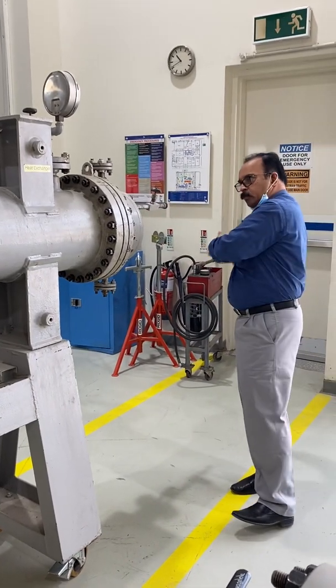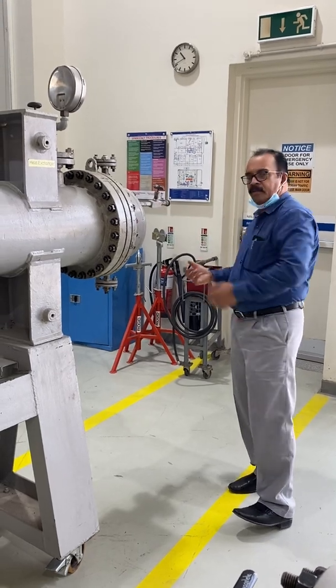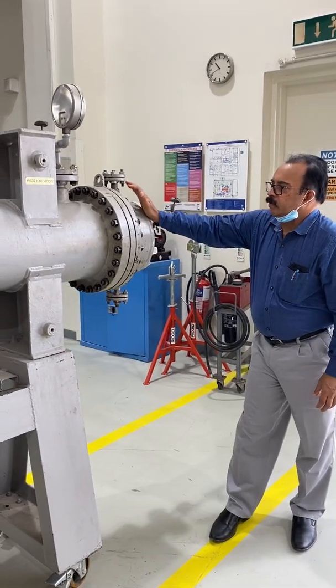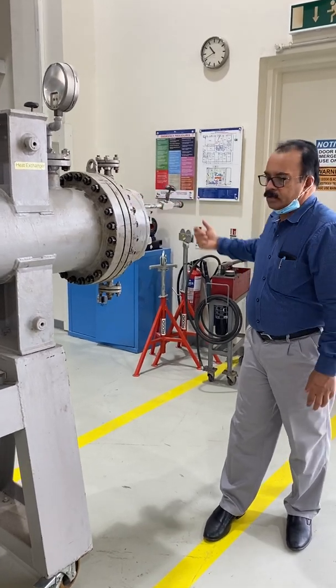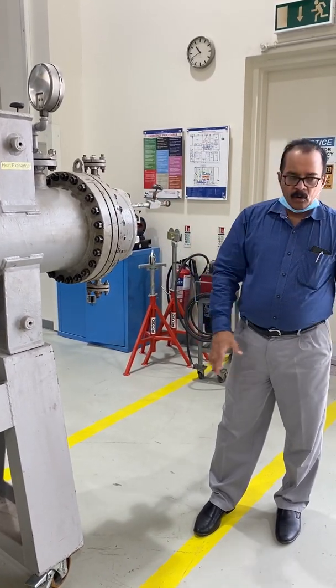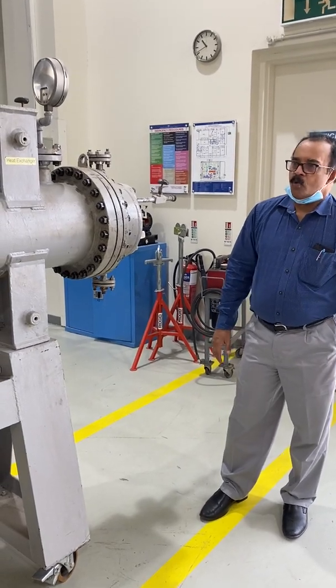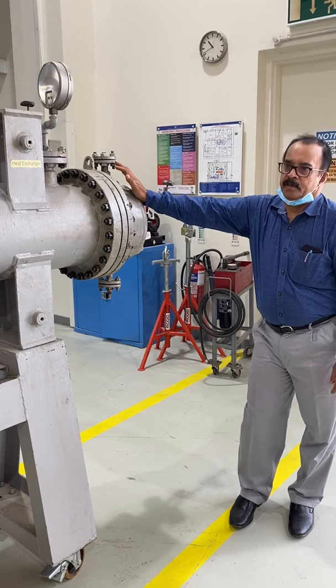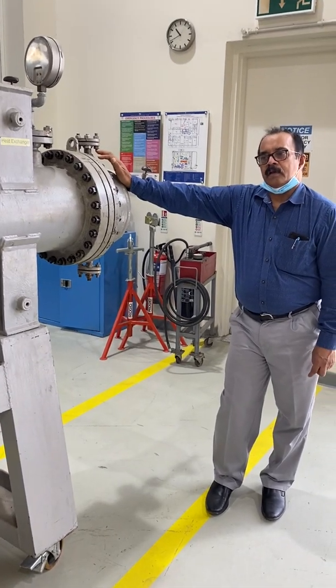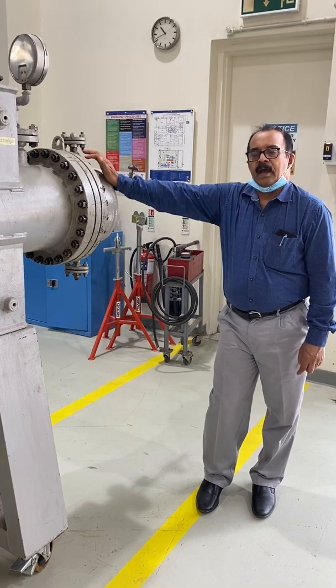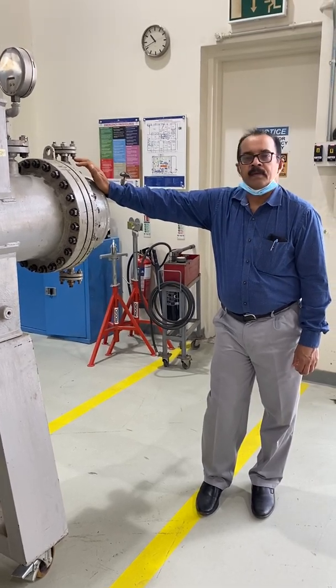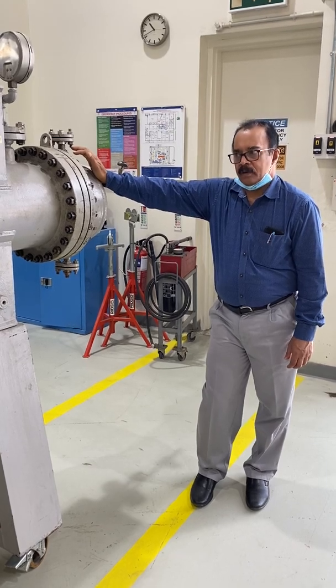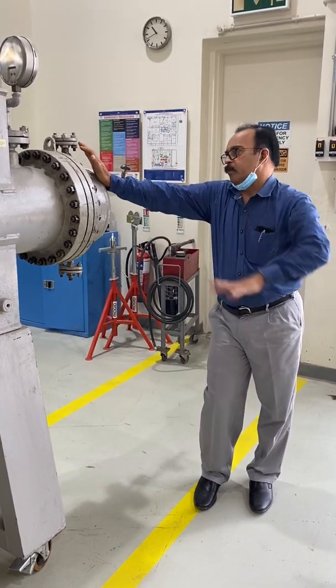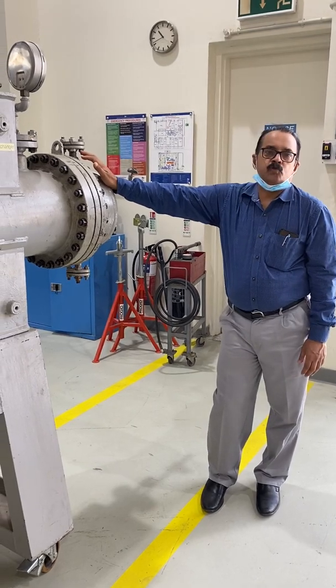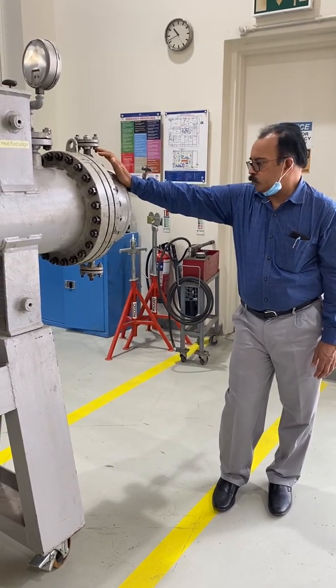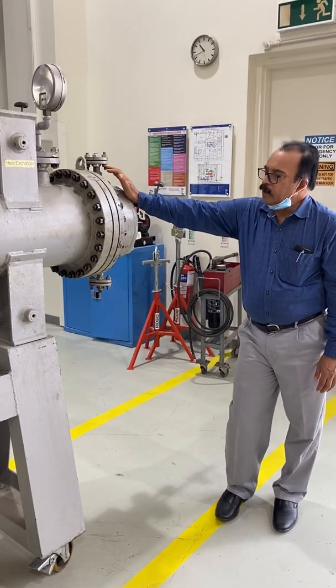You can pull the tube bundle out from the inside, with slings and shackles, using a floor crane or an overhead crane, because it is very heavy, and put it on a table in the workshop. Then you need to wash. Washing is very important because there will be too much dirt and corrosion, and maybe some tubes are damaged. You need to replace those tubes. High pressure water jets are used for cleaning the tube bundle, and the shell side is also cleaned. After cleaning and checking the tubes, if any tube needs to be replaced, replace it. Once the tubes are replaced and everything is cleaned, you can put it back.